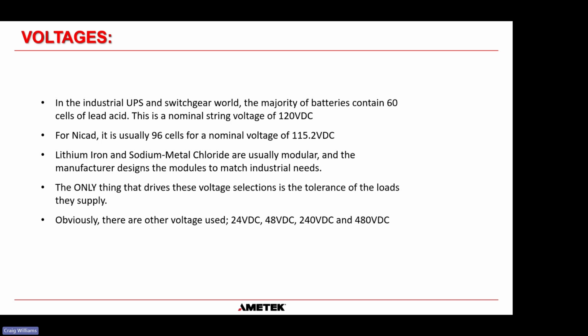Obviously there are other voltages used. 24 volts is used quite a lot offshore for fire and gas systems and ESD systems. 48 volts is telecoms. And we are seeing more UPS manufacturers now using a 240 volt DC bus or a 480 volt DC bus, because the higher the voltage, the lower the current, and therefore they can save on wiring and semiconductors. Everything's cheaper when you work at a higher voltage because it uses less current. They're inversely proportional when it comes to power.